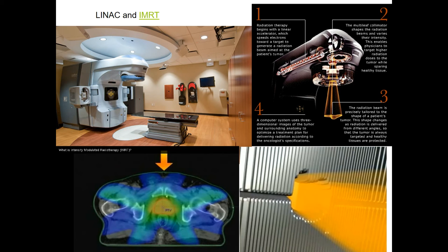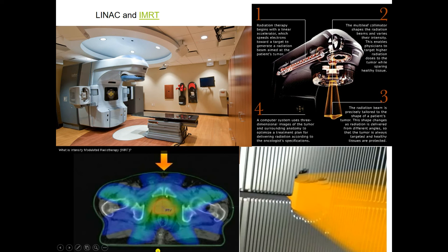The primary tool for treating tumors is the linear accelerator, or LINAC. Windsor Regional Cancer Center has several of these machines — a Varian Clinac. This is a giant x-ray machine not for imaging but for delivering x-ray beams. The patient lies on the bed, the beam comes out of the head, and the unit rotates 360 degrees around the patient to deliver radiation from any desired angle, rather than using one beam that would damage all surrounding tissue.